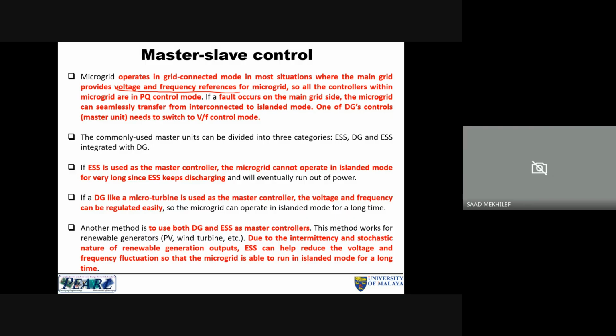But in case a fault happens on the main grid, the microgrid can transfer to the islanded mode. One of the DG controllers, which is the master, needs to switch to voltage and frequency control. So this is what actually happens. If the grid is disconnected, whether due to a fault or whatever, one of the units in the microgrid has to operate in VF control mode.